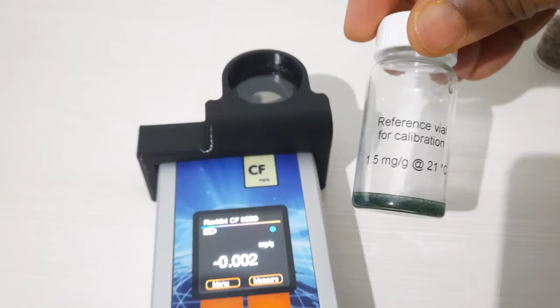Going to menu, just a moment. Yeah, going to menu, sensor settings, enter. Let us do some calibration data. We can press enter. Here you will get the slope. Let us fix the slope at 67 only. This is the default data. Once we do next, it will ask for the offset. No need to do it.